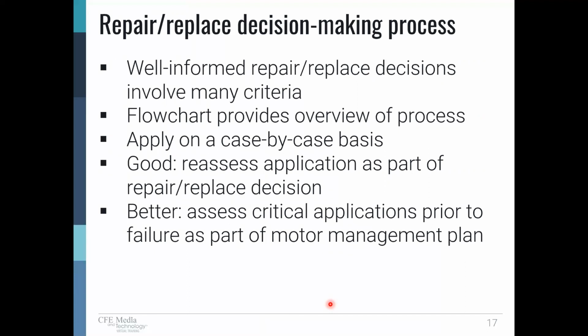Now we're going to move on to another topic, repair-replace decision making. What we want is repair-replace decisions that are made based on, let's call it, hard evidence criteria. In other words, we want to make true decisions, and for that we're going to move in the next slide into a flow chart to provide an overview of the process. And it should be applied on a case-by-case basis. If we've got a motor that runs 24 hours a day and it's 1,000 horsepower, that's one kind of element or criteria. If we've got a 5 horsepower motor that only runs once a day, that's a much less critical machine. We're going to apply a different set of criteria on that, judgmentally and economically and so forth. So a good practice would be to reassess the application as part of that repair-replace decision.